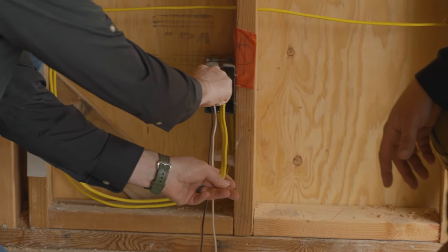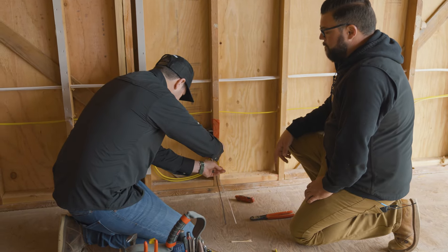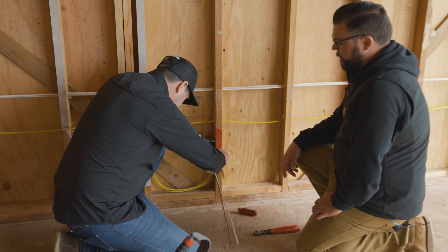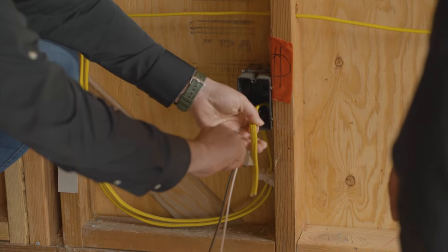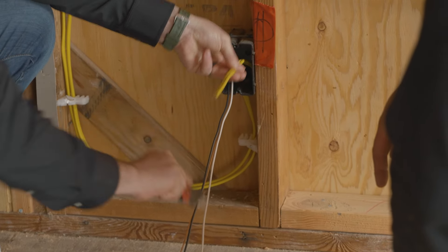I actually like to use these as a gauge to get my wire length. Six inches minimum is code — we like it a little longer, maybe eight. So I like to cut it here, and you're good to go, bud. Watch those fingers. We don't want to use the first aid kit on your first day. After you make up about 200-300 receptacles on this job, you'll be a pro.